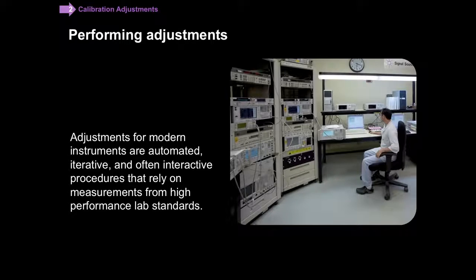Nowadays, the adjustments for modern instruments are almost always automated. Frequently, they are iterative and often they are interactive procedures. In order to get the high performance across an entire measurement band, when we perform adjustments, even the automated procedures sometimes will run for more than an hour. But when it's all over, then you have that instrument tuned up the way that we do them at the factory.